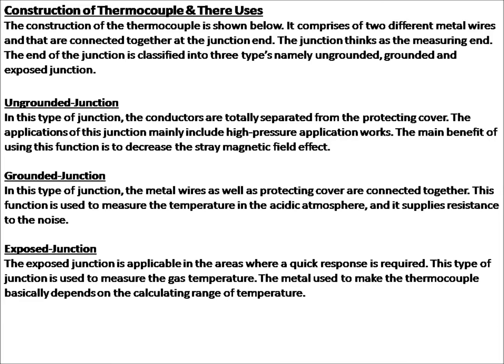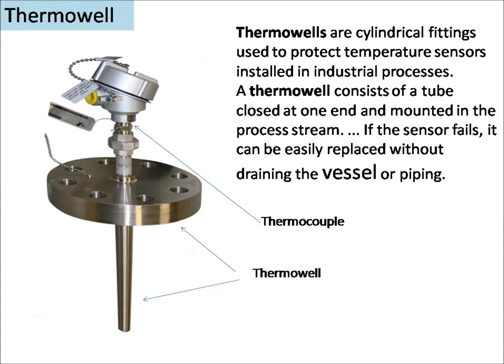Thermowells are cylindrical fittings used to protect temperature sensors installed in industrial processes. A thermowell consists of a tube closed at one end and mounted in the process stream. If the sensor fails, it can be easily replaced without draining the vessel or piping. The thermocouple is inserted inside the thermowell.